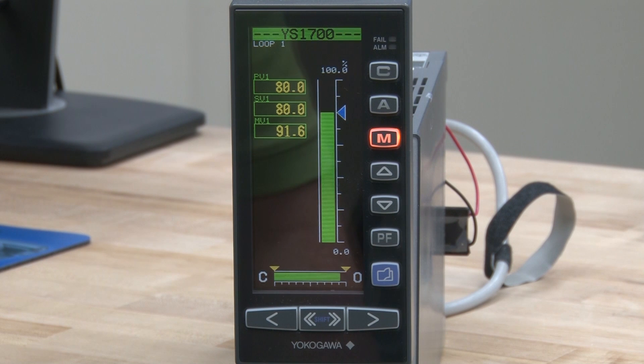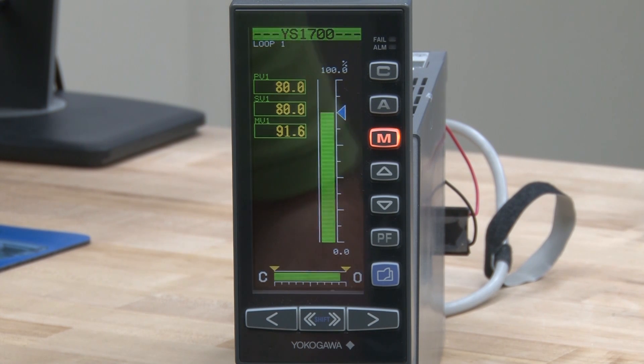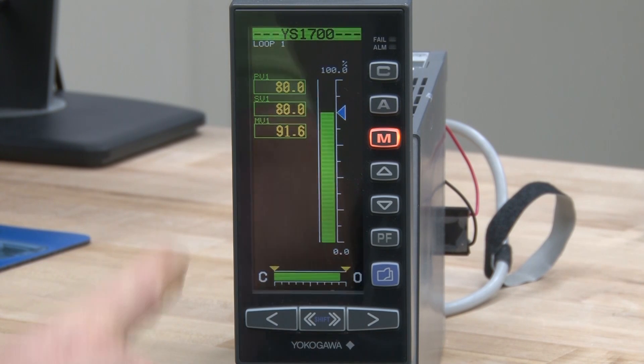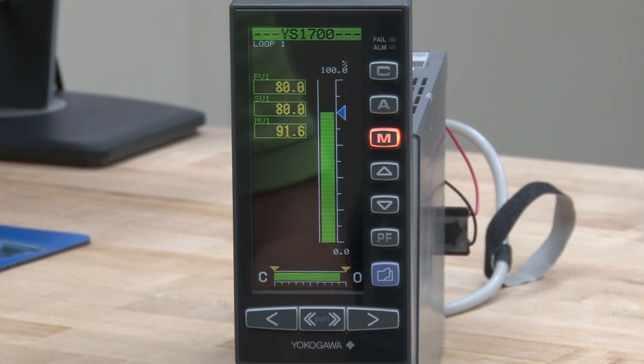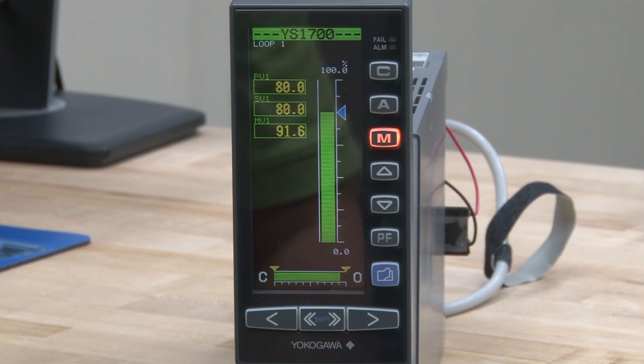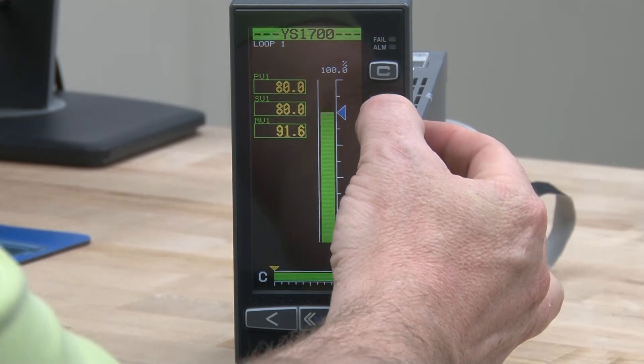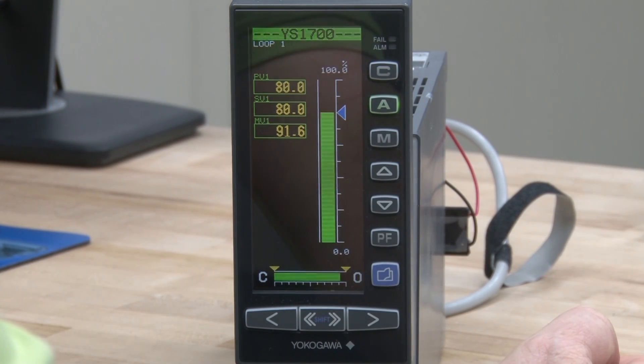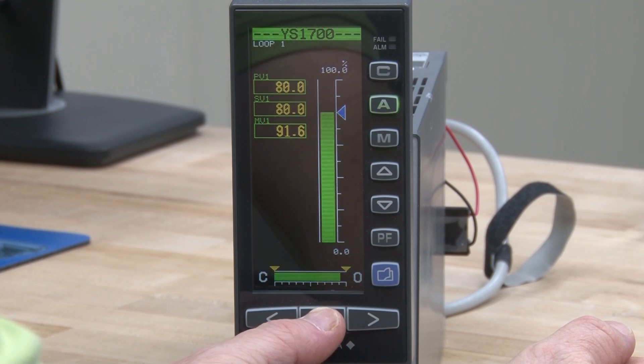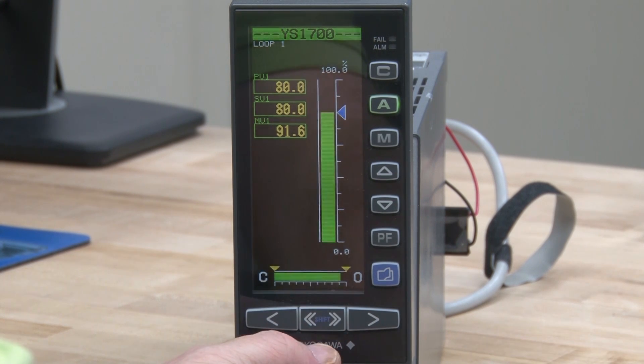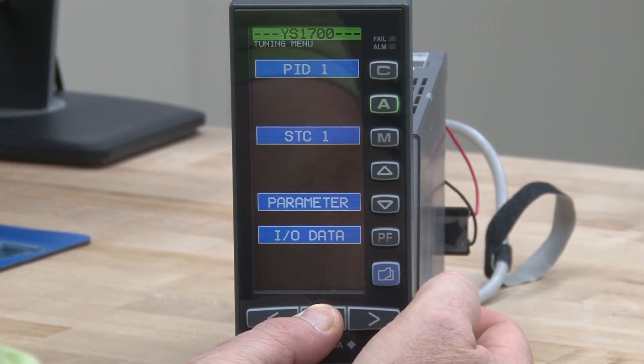Let's go ahead and use the keys on the front of the YS1700 to change the scaling. By default, as you can see here, the controller defaults to a scaling of 0-100% based on your 4-20 milliamp or 1-5 volt input signal for the process variable. To do this, we're going to hold the shift button, which is just below the output display, and push the page key once.